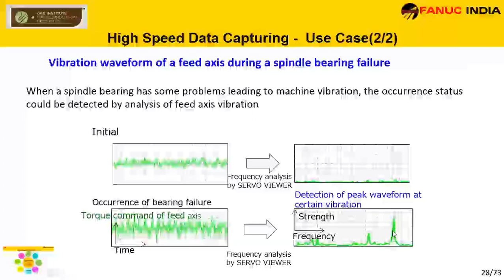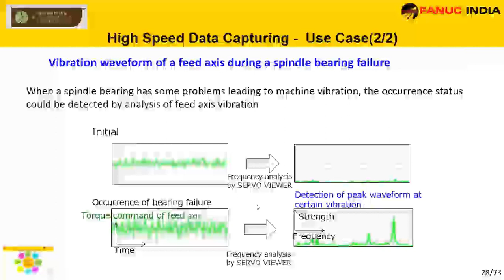One case study for high-speed data capturing use case: the vibration waveform of the feed axis, which we can use for spindle bearing failure detection. Initially, the torque command oscillates normally, whereas when a bearing failure occurs, the torque command oscillates more. This can be converted to Fourier analysis, where we can visualize the difference between the normal and abnormal states, and easily arrive at the conclusion that there is a spindle bearing failure in the machine. This kind of analysis is possible by capturing high speed data from the equipment.